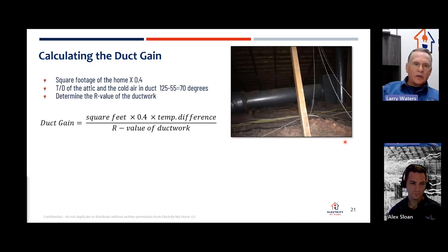Okay, calculating duct gain. In the Sacramento area and generally this area of California, there are a lot of houses with ductwork in the attic space. And this is one of the easiest ways you can calculate what your capacity savings can be by replacing and burying this ductwork. And we see this very picture up in attics a lot. You go to an older house and you look up there and you see a return air that's raw metal.